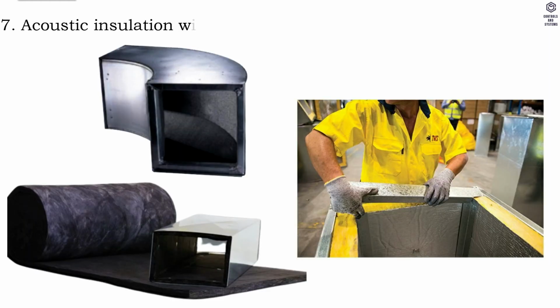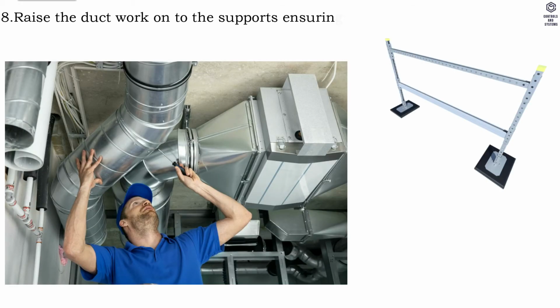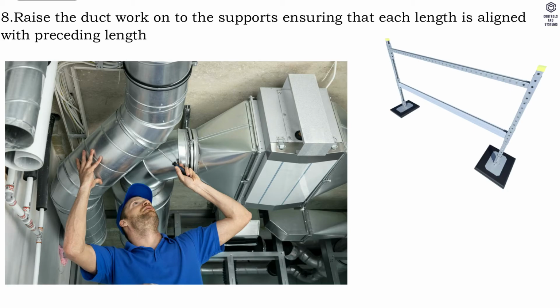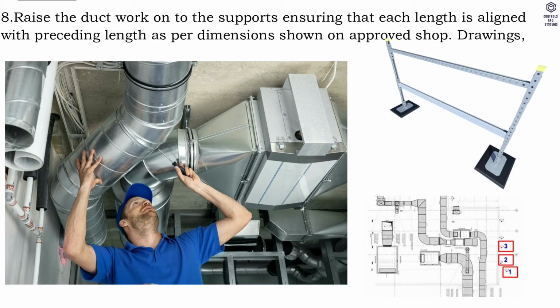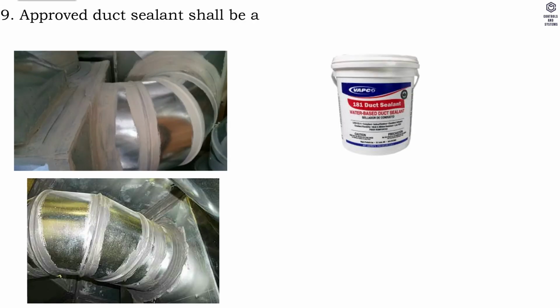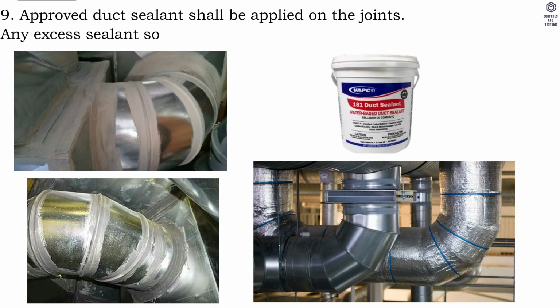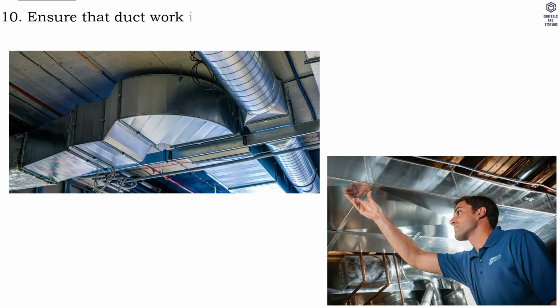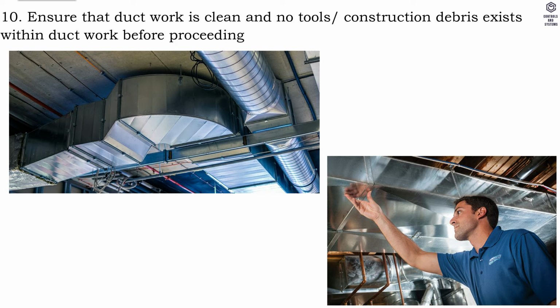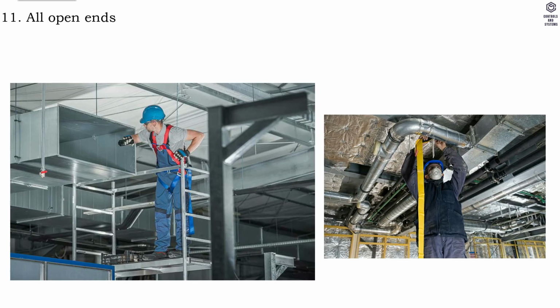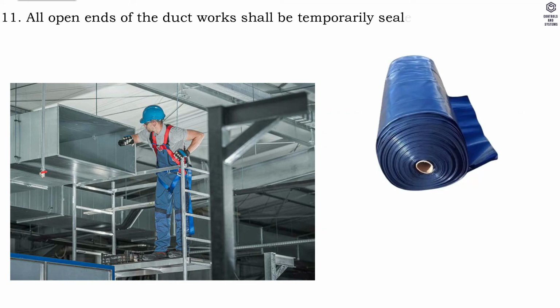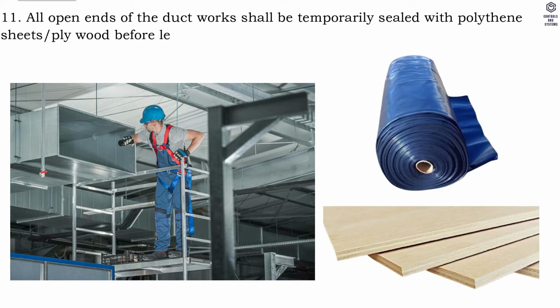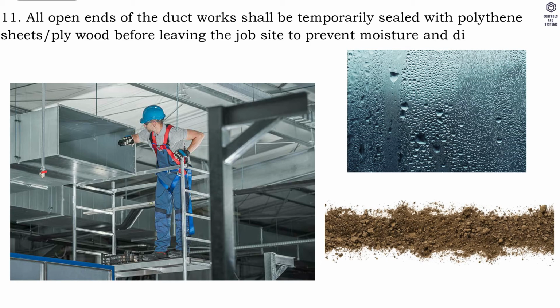7. Acoustic insulation will be carried out wherever required. 8. Raise the ductwork onto the supports, ensuring that each length is aligned with preceding length as per dimension shown on approved shop drawings. 9. Approved duct sealant shall be applied on the joints. Any excess sealant shall be removed so that the joint is left in clean and tidy condition. 10. Ensure the ductwork is clean and no tools or construction debris exists within ductwork before proceeding to next length. 11. All open ends of the ductworks shall be temporarily sealed with polythene sheets or plywood before leaving the job site to prevent moisture and dirt.